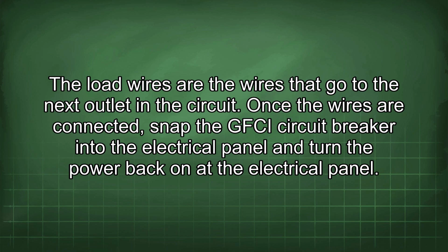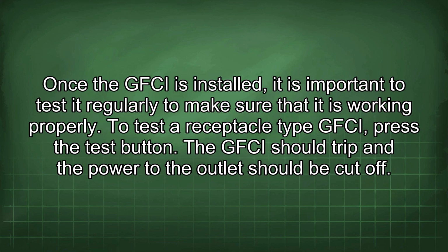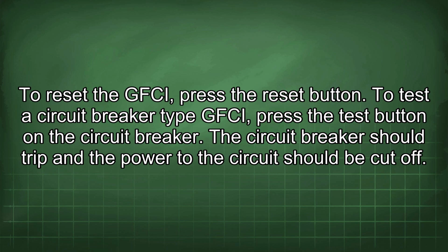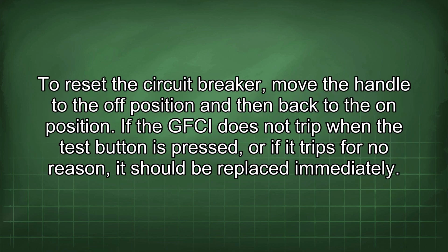Once the GFCI is installed, it is important to test it regularly to make sure that it is working properly. To test a receptacle type GFCI, press the test button. The GFCI should trip and the power to the outlet should be cut off. To reset the GFCI, press the reset button. To test a circuit breaker type GFCI, press the test button on the circuit breaker. The circuit breaker should trip and the power to the circuit should be cut off. To reset the circuit breaker, move the handle to the off position and then back to the on position. If the GFCI does not trip when the test button is pressed, or if it trips for no reason, it should be replaced immediately.